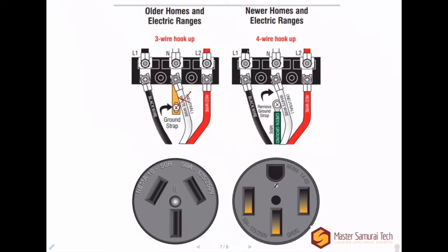That's why the whole idea with the four-wire hookups was to separate neutral and ground, recognizing that they serve very different functions. There's really no good electrical reason for ground and neutral to be tied together — they serve two different things. So now, in the case we just described, where you get a charged chassis and the neutral wire burns off, since we do have a valid ground connected all the way back to the circuit breaker box, it's going to trip the breaker in all likelihood. That's what should happen. So it's sort of redundant, but they really are functionally different wires.